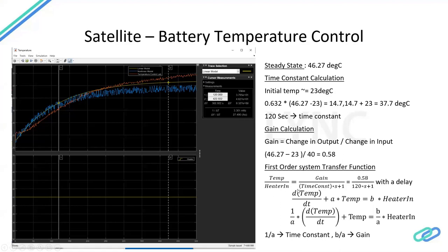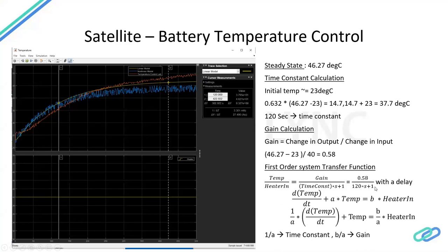This gives us a basic transfer function for the first-order system: Gain / (Time constant × s + 1) — where s is the Laplace variable used in transfer functions. The transfer function of Temperature / Heater Input is: 0.58 / (120s + 1). A transfer function describes how the output variable changes for a given input — here, the output is temperature and the input is heater input. This first-order behavior was derived entirely from measurement data, with no physics required.